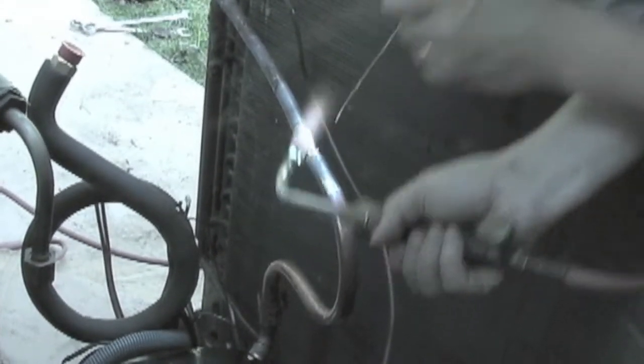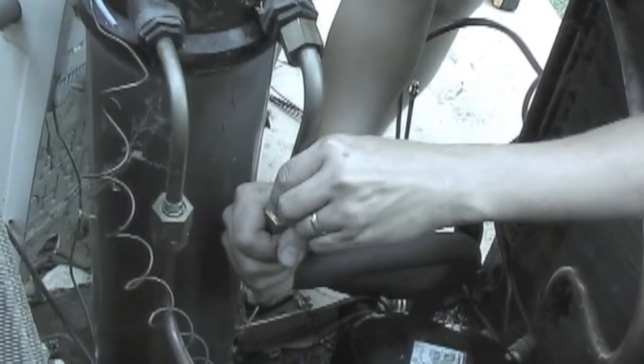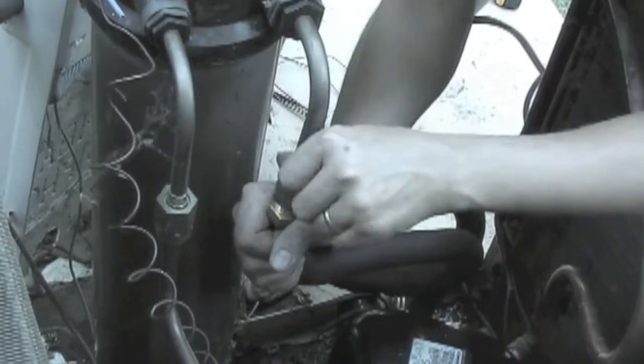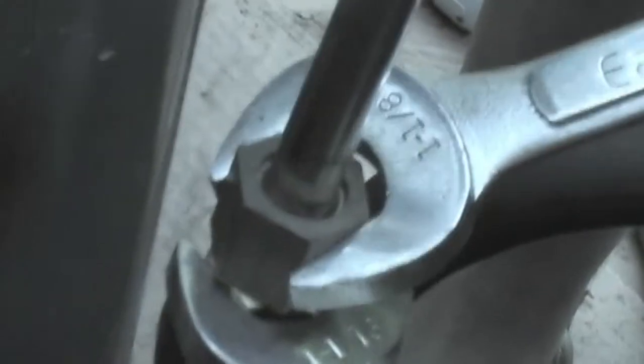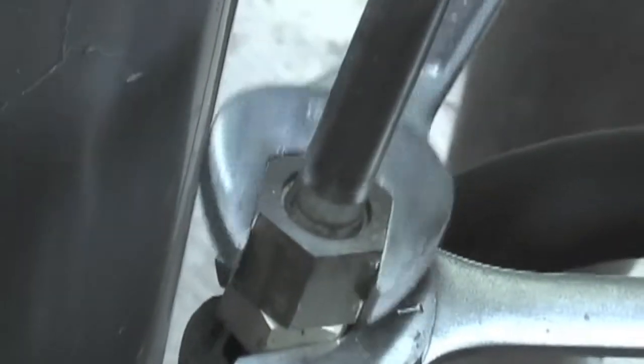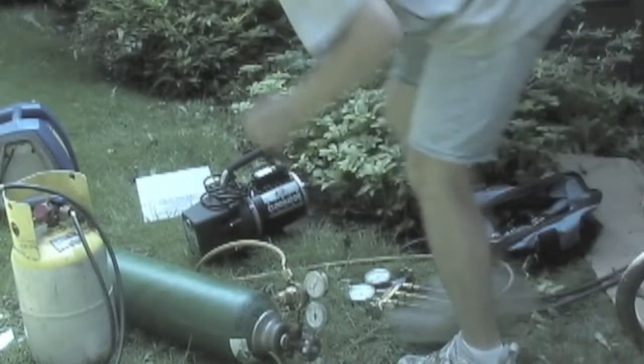Reconnect the heat exchanger to the brass fitting. Be sure to install the black o-ring and white seal ring inside this fitting. Tighten the fitting using the two large wrenches. You can use Loctite to seal these threads. The refrigerant system is now closed and you should pressurize with nitrogen to check for leaks.